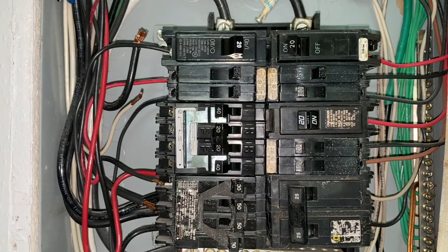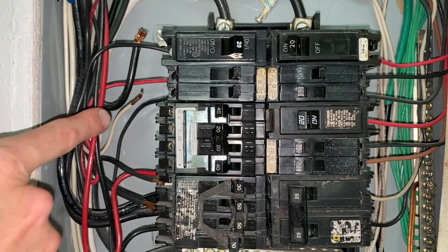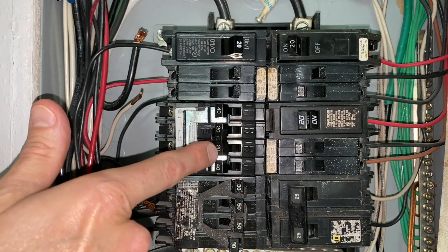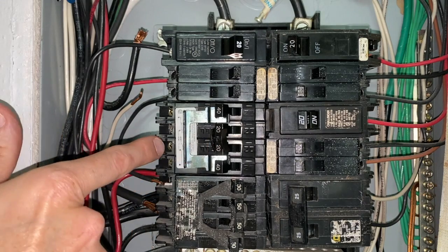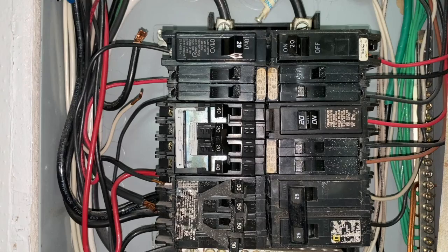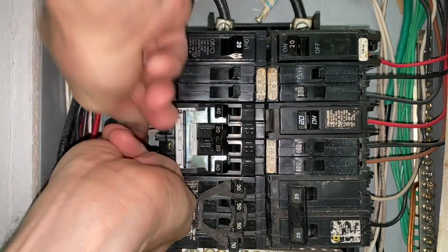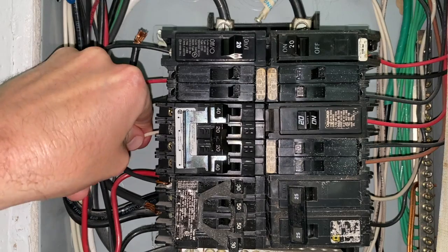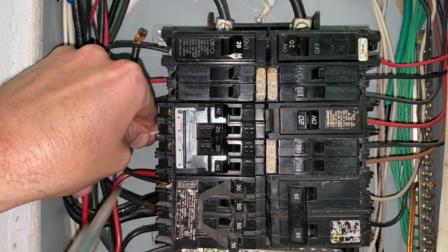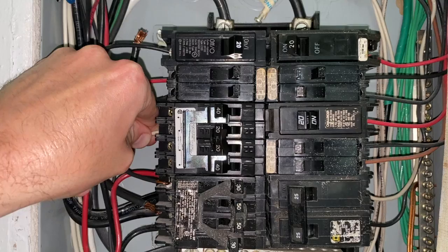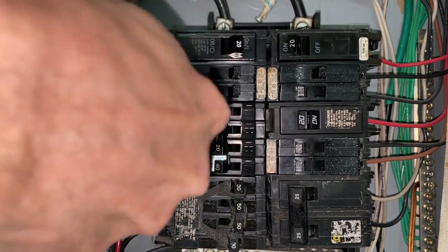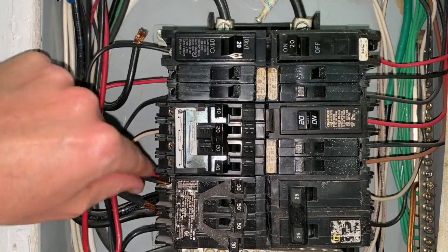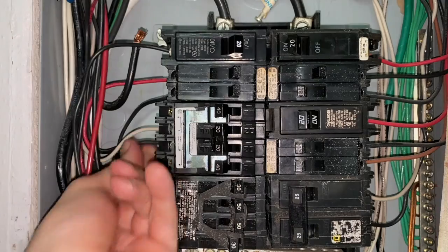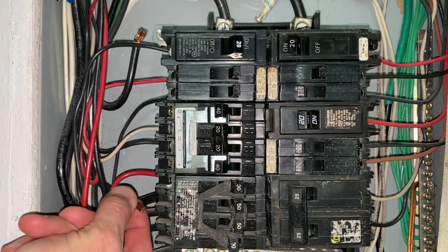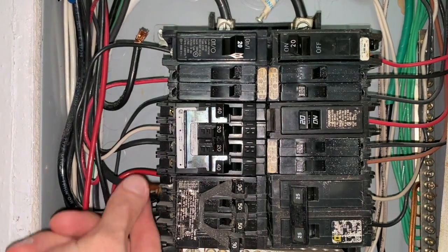From here we will reverse the steps in regards to the wires, and we will secure the white wire followed by the lower black wire that feeds into the lower 20 amp pole of the 2-pole breaker, and then the 2 outer and thicker black cables. And as you tighten these in place, I recommend holding the wire as you screw them tight. Do not over tighten them, but you definitely want them snug. Followed by the lower. And again, followed by the 2 outer and thicker 40 amp wires.